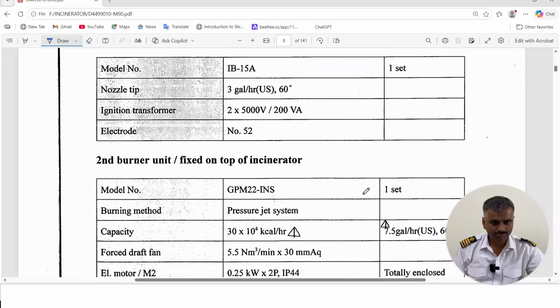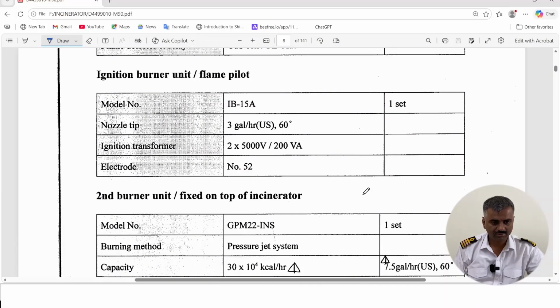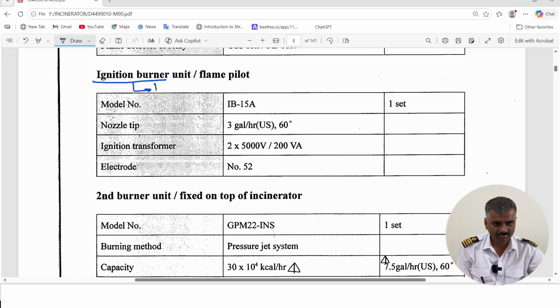So guys, now we will move to the next topic, the ignition burner or the pilot burner. Don't get confused with the name. If you see somewhere in this manual written as ignition burner, basically it is the pilot burner which is going to give you first ignition. Okay, so from here ignition will take place. So this pilot burner will have a set of electrodes, two electrodes for producing spark.